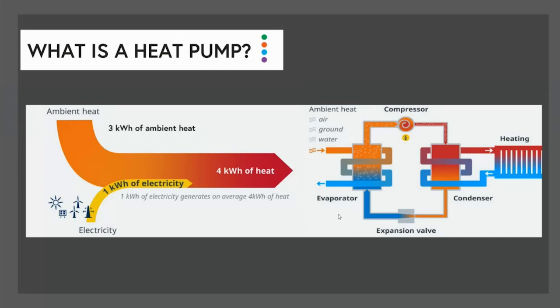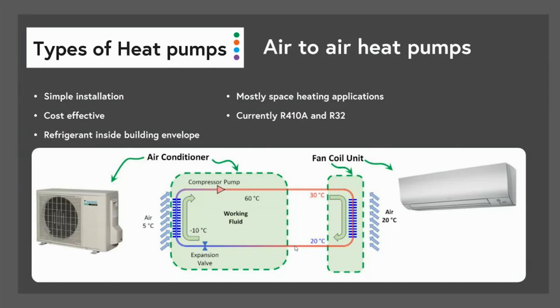So we've got a hot liquid then coming out of the condenser going to the expansion valve. The expansion valve reduces the pressure dramatically, which plunges the temperature, and now you have cold liquid going back into the evaporator, and then the whole process starts again. So that is the basic premise of how a heat pump works. And if you've got any questions about that, we can kind of deal with it at the end. But hopefully that was a good enough explanation to get us going. So let's move on. So types of heat pumps.